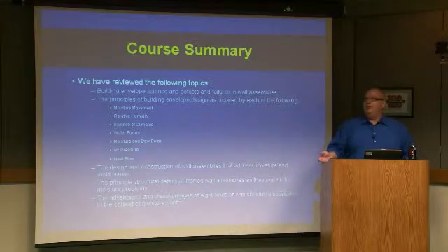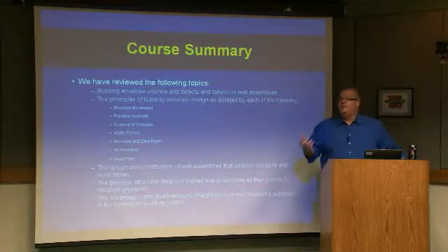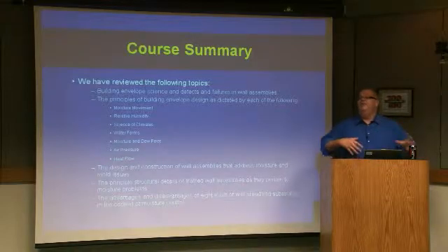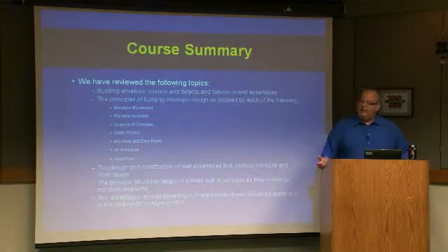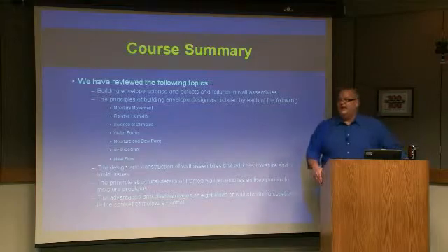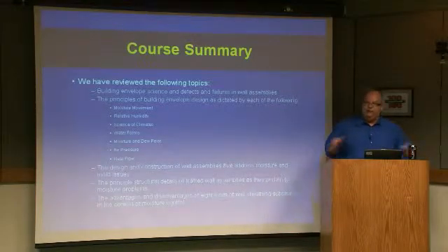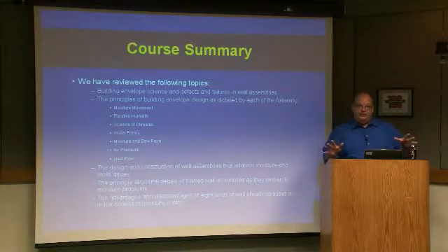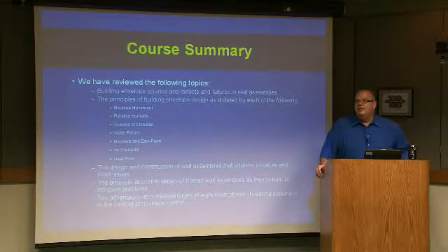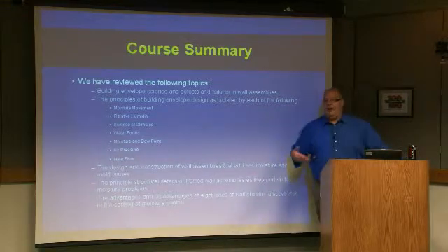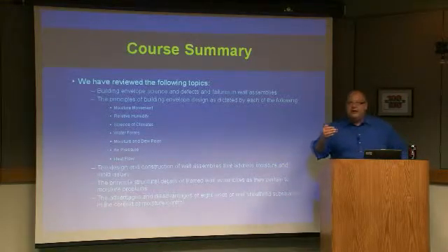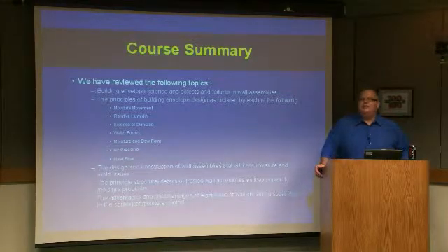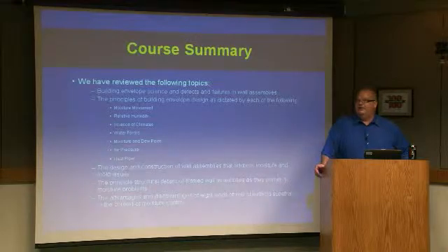Warm air can hold more moisture than cold air, so typically hot air masses do have more moisture in them. And if you take that mass and start cooling it down, the moisture is going to come out. Where it comes out is 100% RH, and that's the dew point. So what we worry about is creating cold surfaces, which creates high humidities. What was a low humidity before sees that cold surface and becomes a high humidity. So what was 35% relative humidity inside your house, as it goes through that wall in the wintertime and gets to colder surfaces, if it gets around 35 degrees Fahrenheit, it's up to 100% humidity. And that's when it starts to condense.